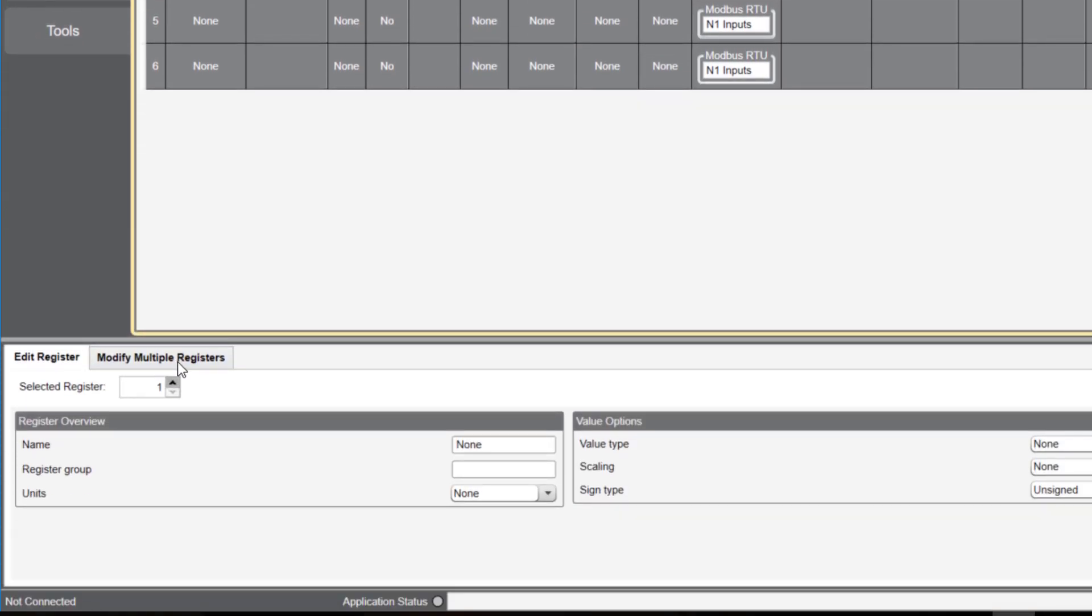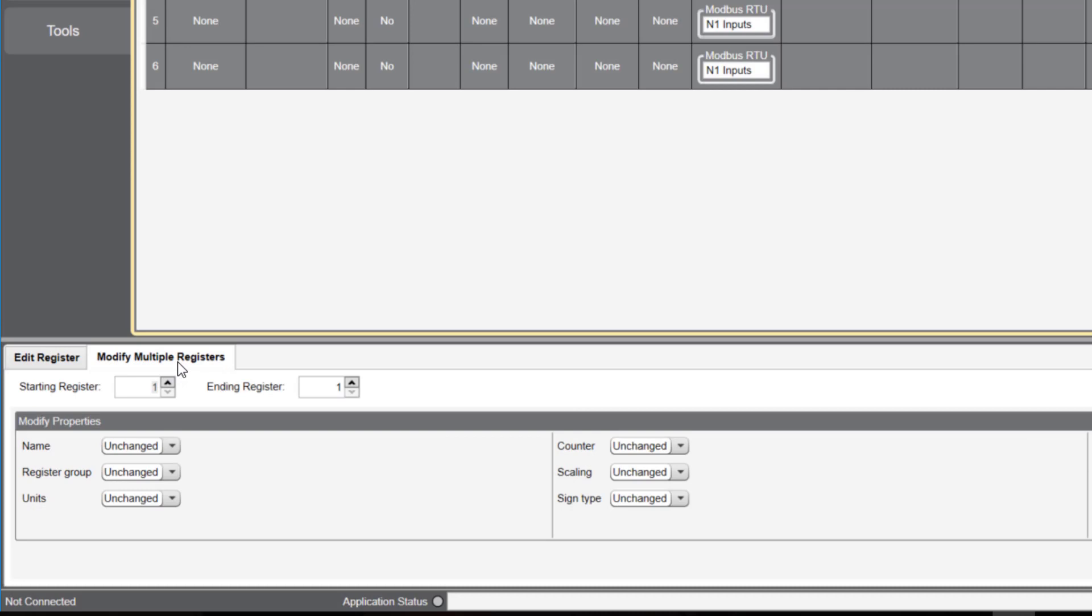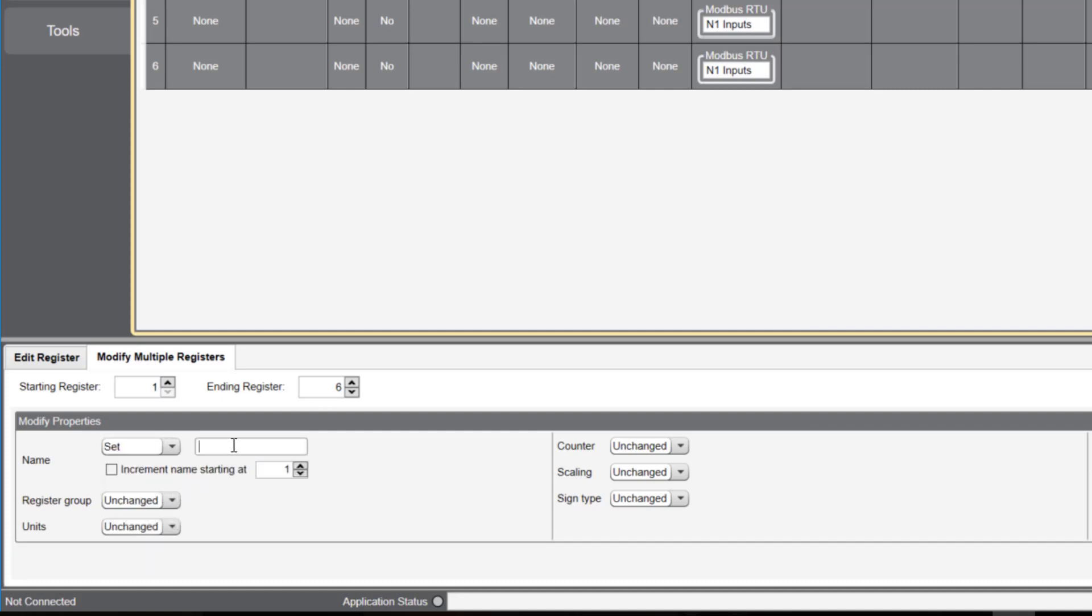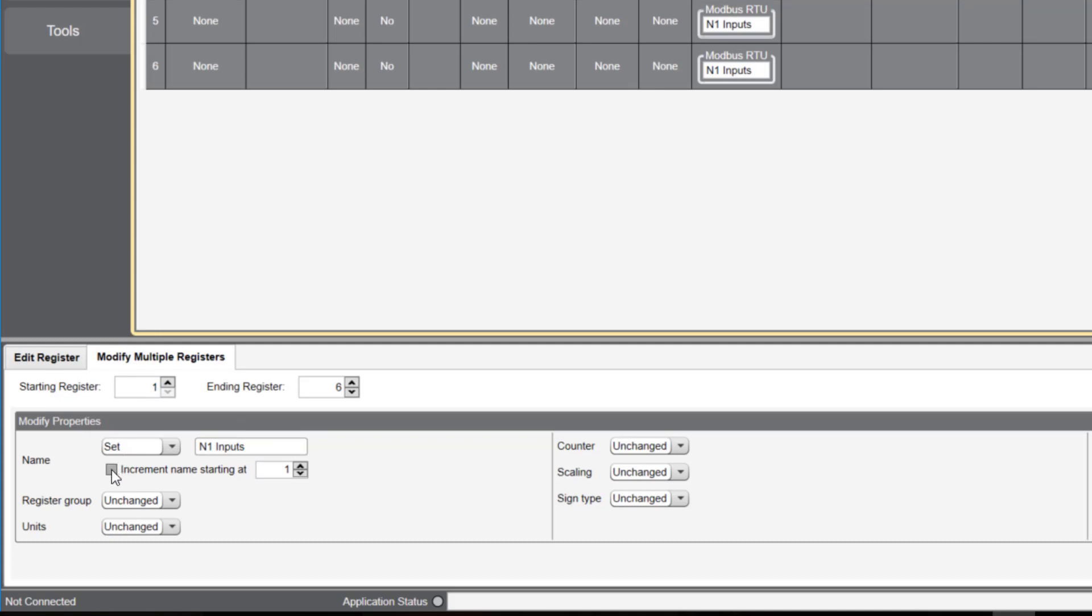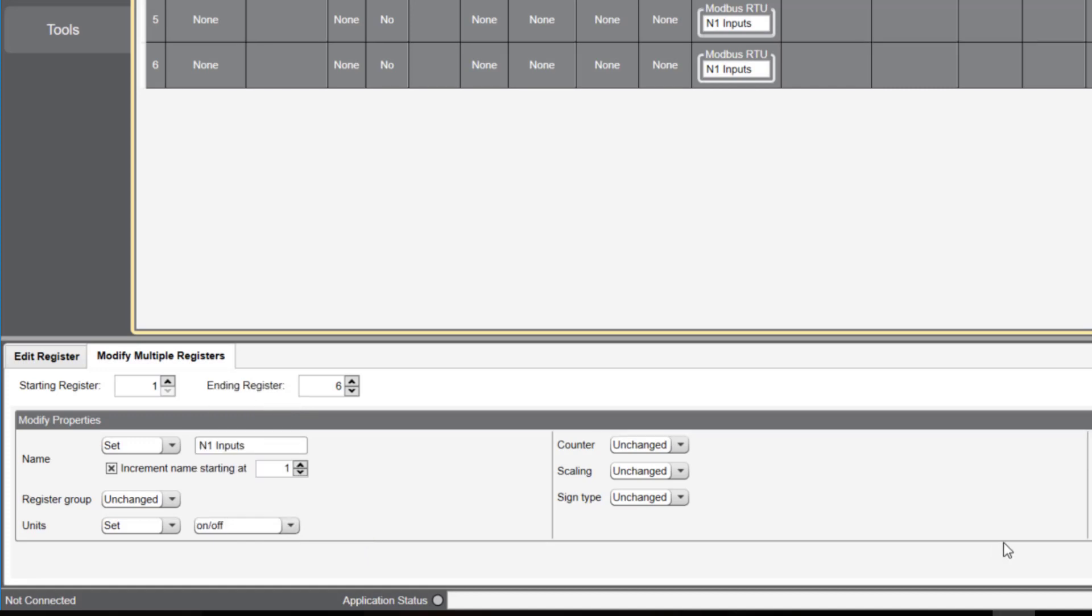Since we have multiple registers, I'm going to use the modify multiple register tab to automatically number them from 1 through 6. I'll click on name and set name to node 1 inputs. I'll click increment to automatically number the registers from 1 to 6. I'll also click on units, then set. You'll notice you have several options to choose from. Since my inputs are discrete, I'll select on-off.